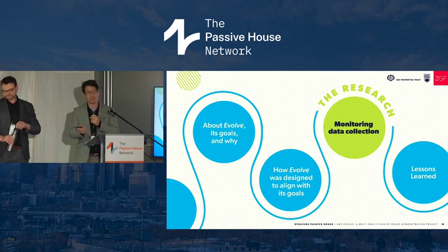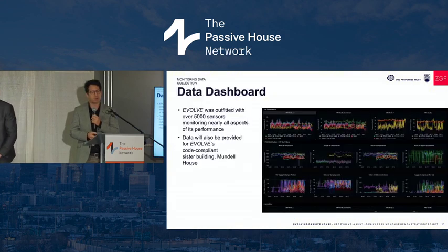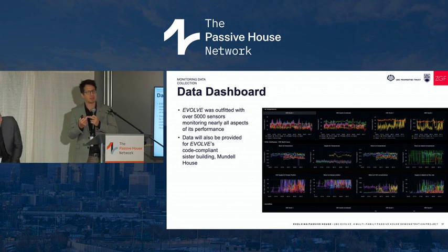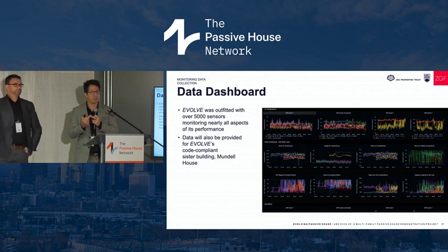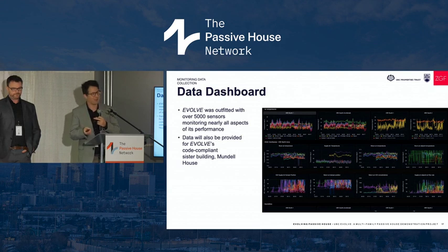Here is a residential building, somewhat in this gray area between the university and the real world, where we outfitted each dwelling with a VAV supply air system for the tempered air. We have flow meters, temperature sensors, sensor points on damper controls, so we know what the thermostats are trying to do. We have the HRVs monitored at each point from the wheels to the coils. We have a very full, heavily engineered data infrastructure, which we're now just digging into.